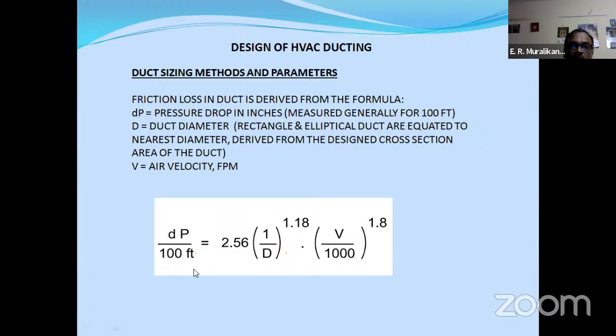So this is the formula for that: dP per 100 feet is equal to 2.56 into 1/D to the power 1.18 into (V/1000) to the power 1.8, where D is the duct diameter. If you have a rectangular or elliptical duct, it will be converted to an equivalent diameter. Now, area is equal to pi D squared by 4. So if you have a 4 square feet area in a rectangle, you can easily apply the formula pi D squared by 4 and get the equivalent round size.